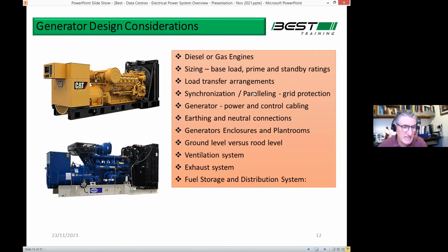Ventilation system: they take an enormous amount of air, which isn't shown here in the diagram. So to cool that radiator down, when you're driving your car, you're driving against the wind, so the wind is blowing through your radiator and cooling it down for you. The generator is sitting in a container or in a room, so the fan has to be driven by the engine, and it has to pull in vast volumes of air, which creates lots of noise. So you have to put it through an attenuator to reduce the sound pressure, etc. So there's lots of considerations taken into account.